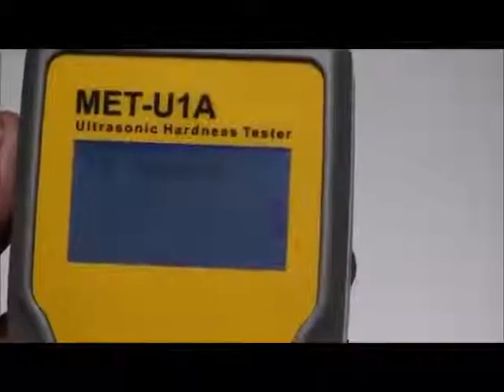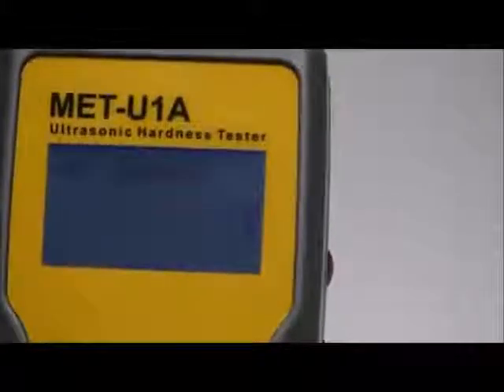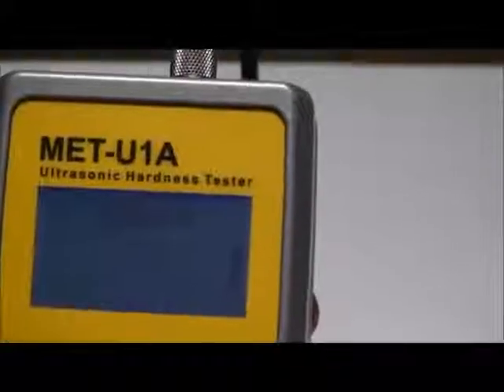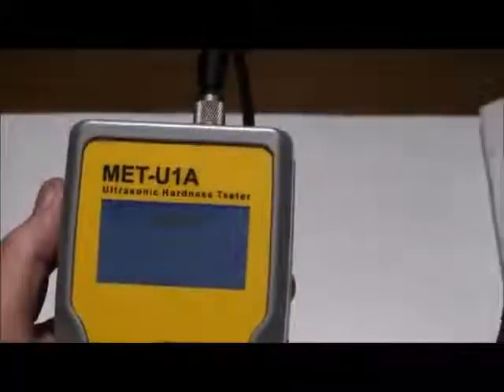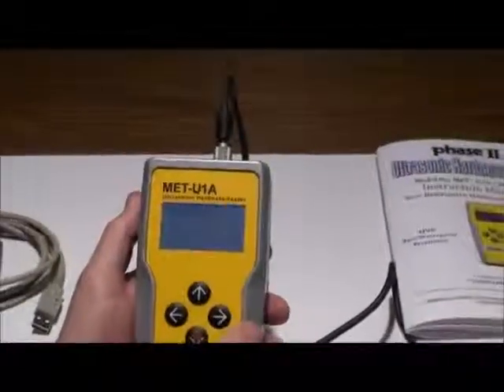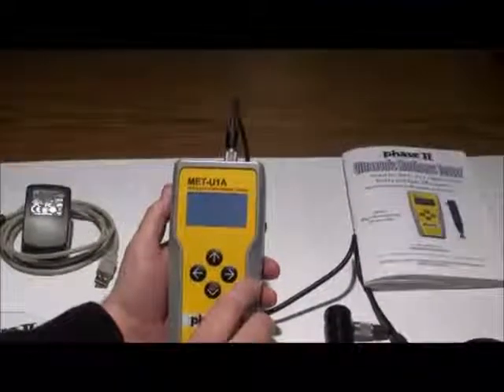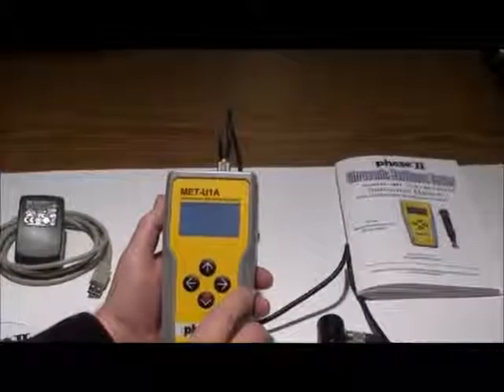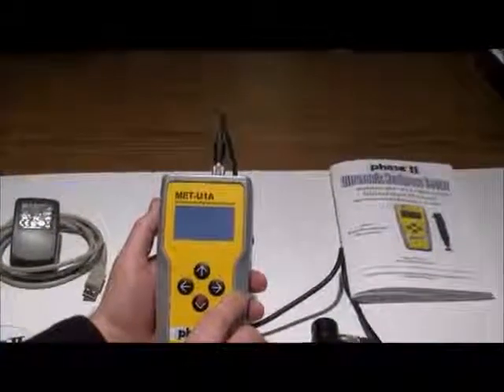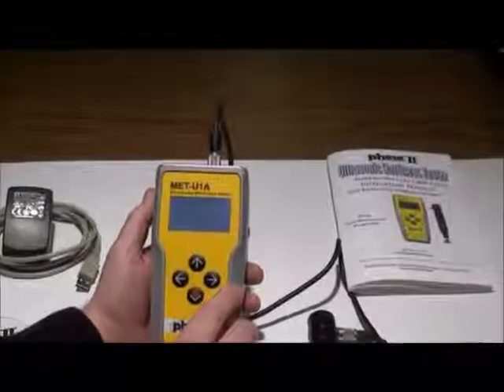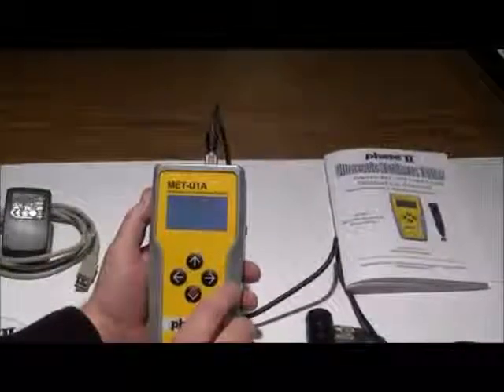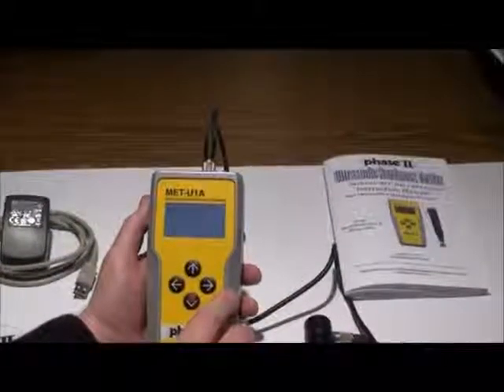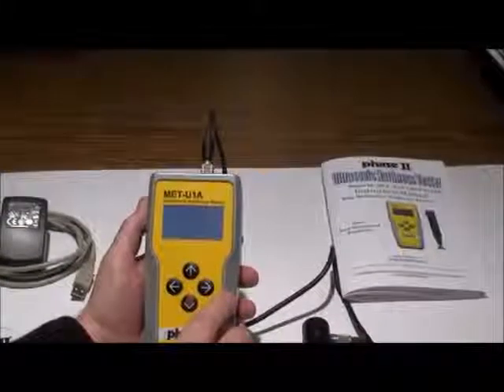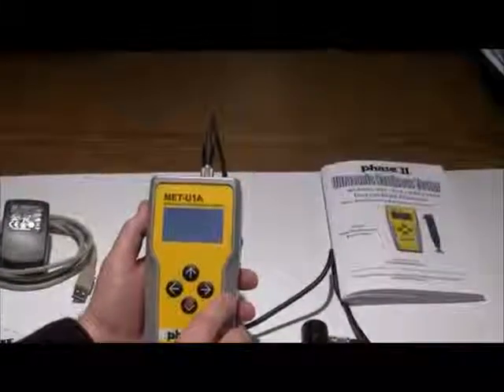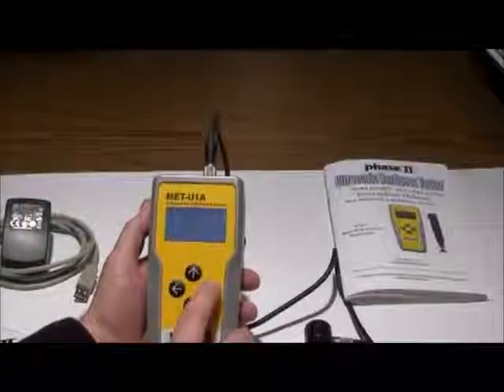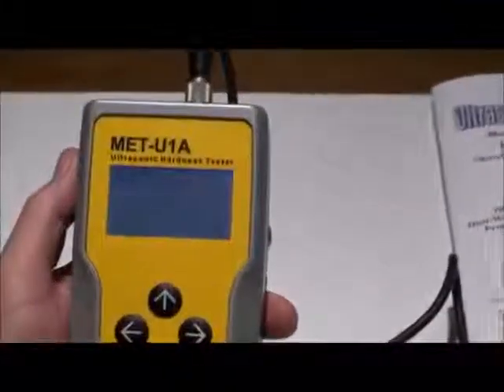Continuing to scroll right, H0, H1, 2, and 3 are all open programs. We can build any scale for metals as long as we have 2 reference blocks or workpieces of the same material being tested with a known value, both high and low on the scale. This programming is easy and takes no more than 5 minutes. The operator can easily make programs if necessary with our engineer over the phone in no time at all. Clicking down after the confirmed scale is selected will allow you to test in that scale.